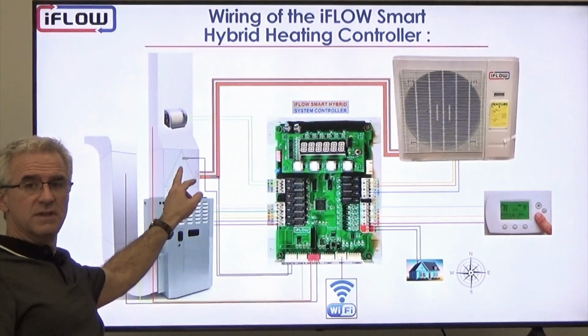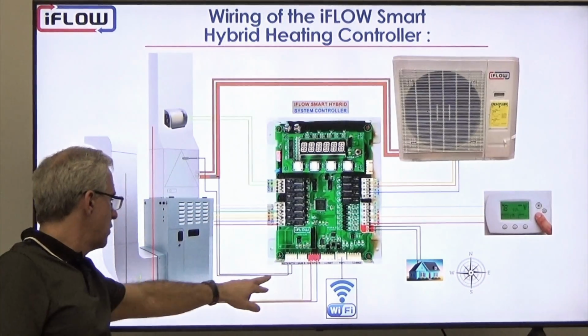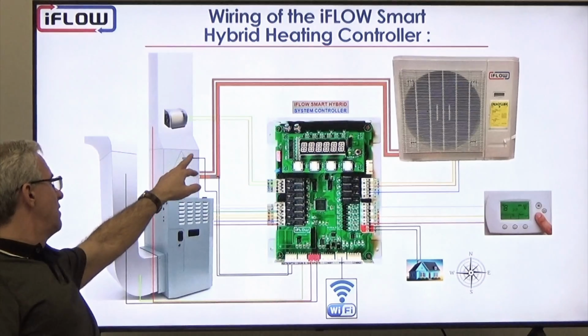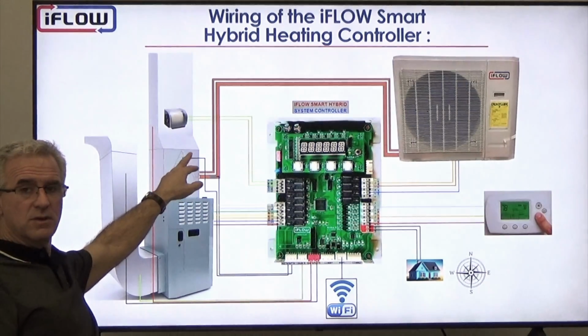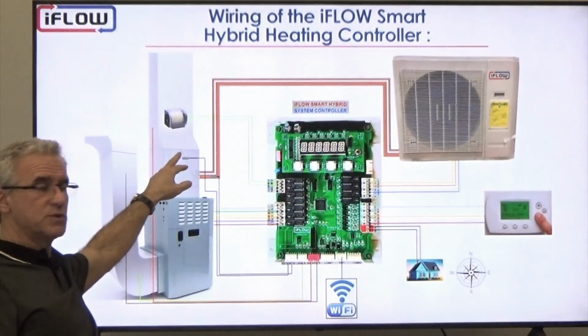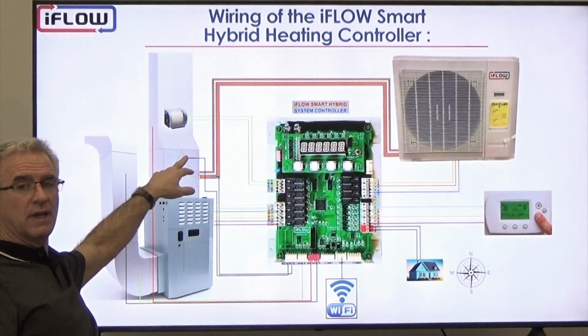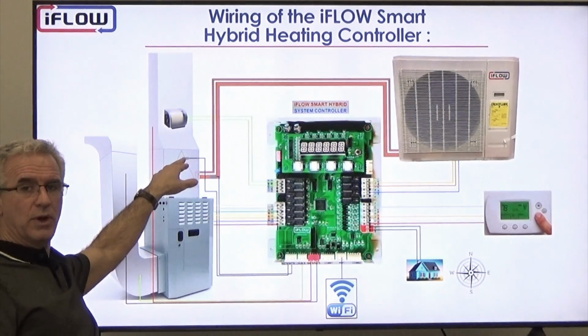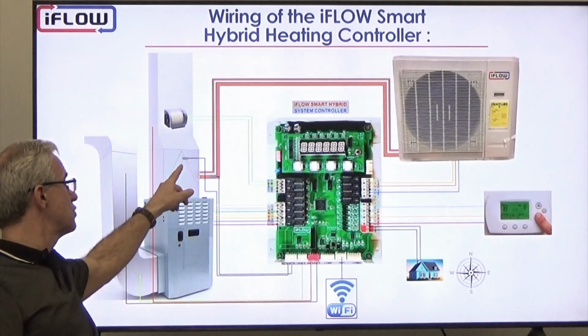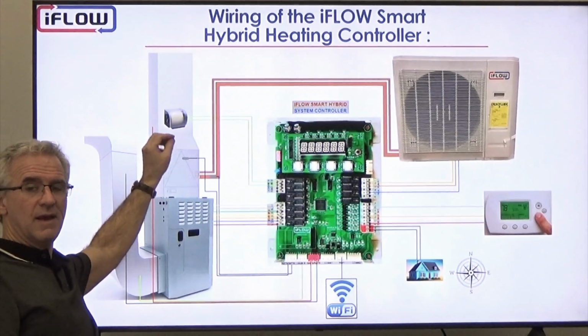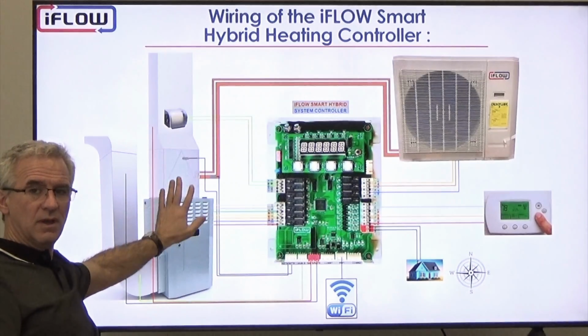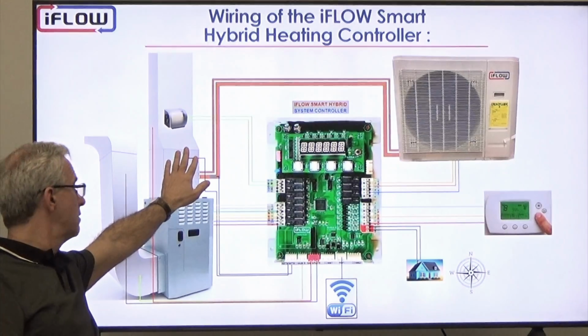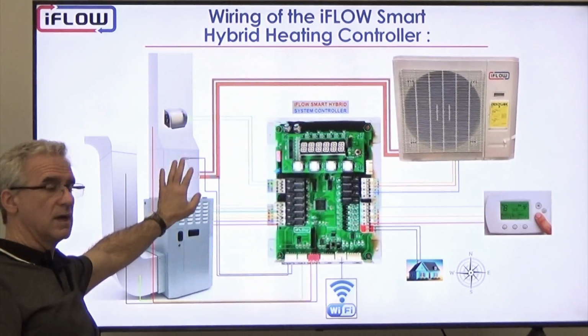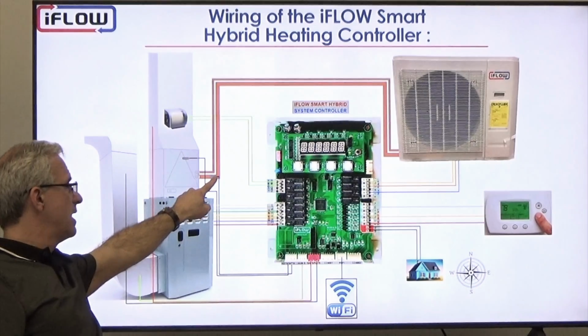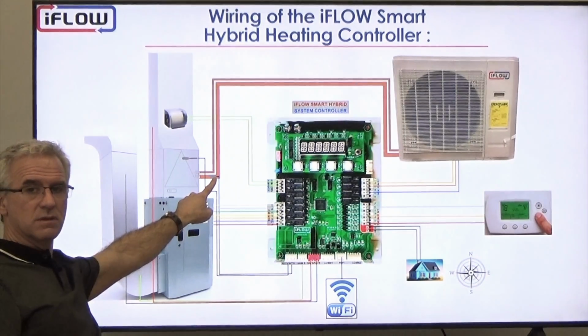We have two more sensors. Again, these are going to the evaporator. We have our freeze protection sensor or our AC evaporator temperature sensor. That will connect to the top of your evaporator coil in between the fins or strapped to an elbow near the top. And it's going to read the air temperature coming off the top of the evaporator, both in heating and cooling applications. And then we have a suction line temperature sensor.